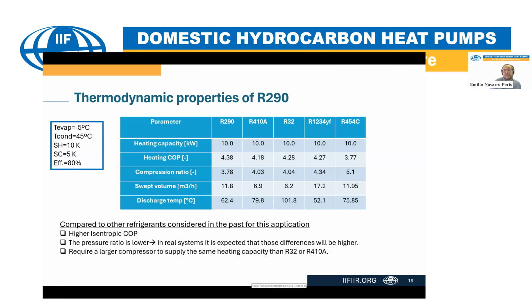Based on that, this table shows the results we obtained for the different refrigerants. We can see that the heating COP for propane is the highest among the fluids considered. It's true the differences are not very large—comparing propane with R410A or R32, the difference is around 3-4%—but it is better.